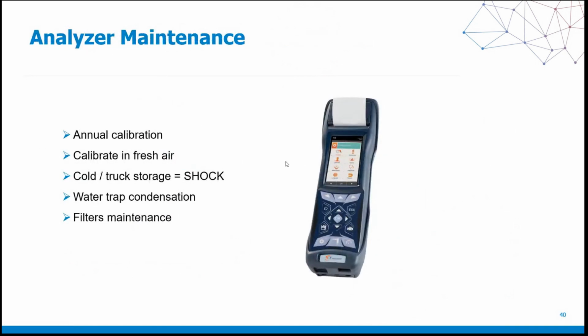Analyzer maintenance. Just a couple of things I like to touch upon here before we conclude for the day. First of all, annual calibration. In a perfect world, a combustion analyzer should be sent in every year for annual calibration. Your calibration certificate is a legally binding document that shows that your combustion analyzer has been tested and evaluated for proper operating conditions for the time period that the calibration certificate covers.